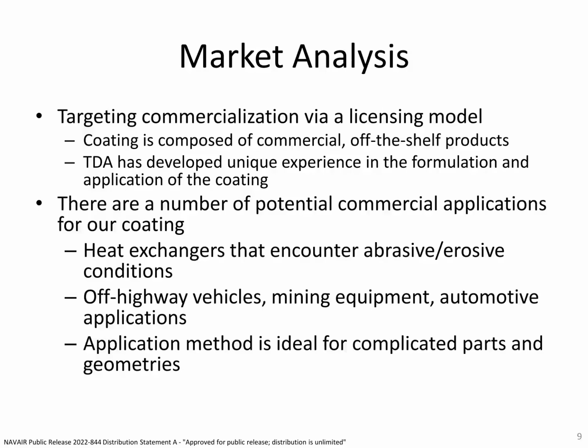Market analysis. We are targeting commercialization of our coating via a licensing model. Although the coating is composed of commercial off-the-shelf products, TDA has developed unique expertise in the formulation and application of the coating. We see a number of potential commercial applications for our coating, in both the defense and civilian sectors. Our coating could benefit really any heat exchanger that encounters dirty, dusty, or abrasive conditions when the manufacturer or operator wants to increase the maintenance intervals between heat exchanger cleanings.